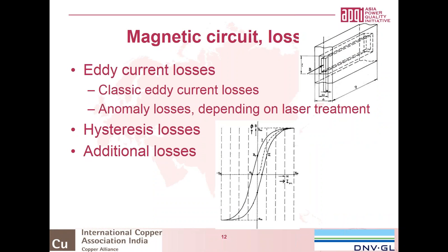If you look at the magnetic circuit, the losses they have, basically there are some losses. I think most of you might know within those very small sheets you could have eddy currents. There you have your normal eddy currents which you can calculate very easily, because there will be a current induced within a sheet, and then you can calculate the losses. Also you can look at the laser treatment, and they can also have some losses, and also the G-joints where the core is connected to each other. You can also have some additional losses.